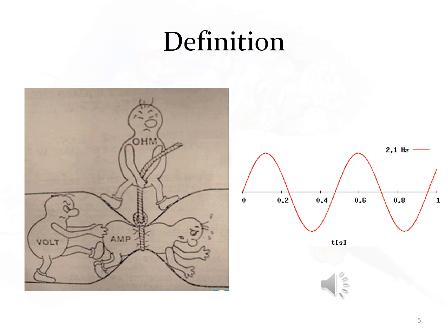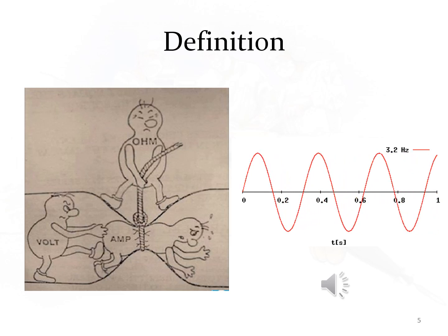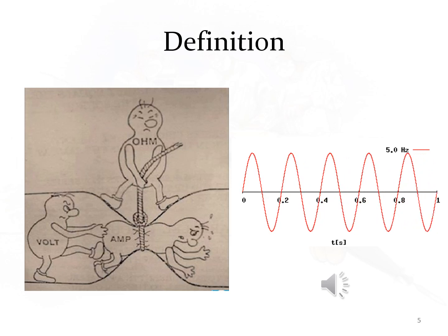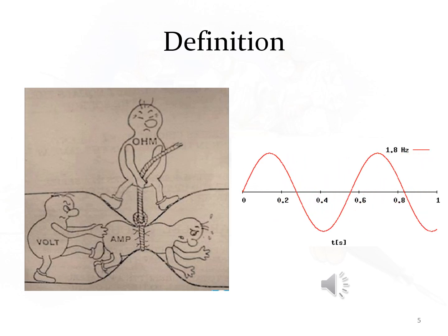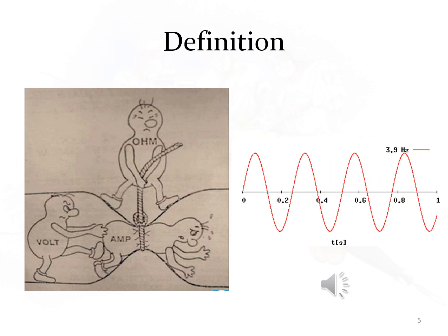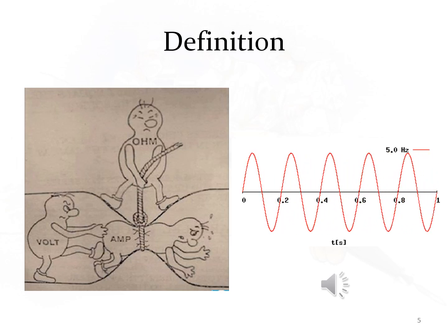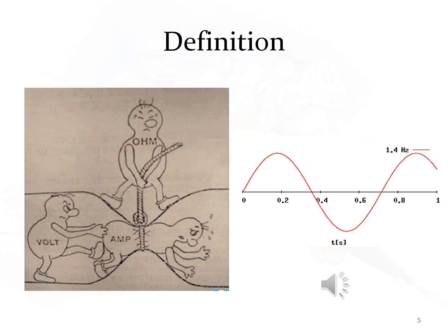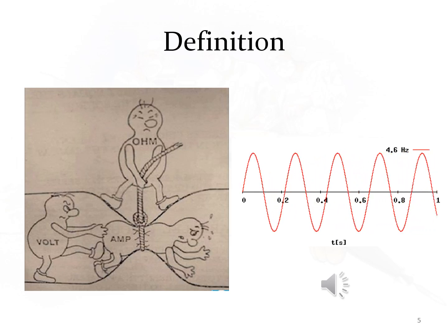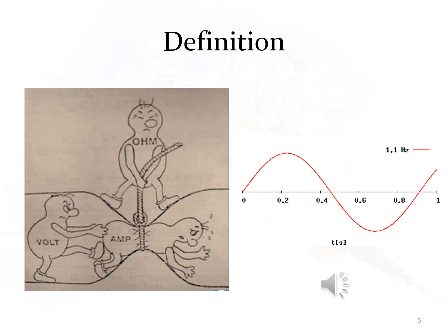In electrosurgery, voltage is provided by the generator. Current is delivered to the tissues through the electrode tip of the instrument. Resistance to current is inherent within all human tissues. The higher the inherent resistance, the greater the voltage needed for the current to pass.